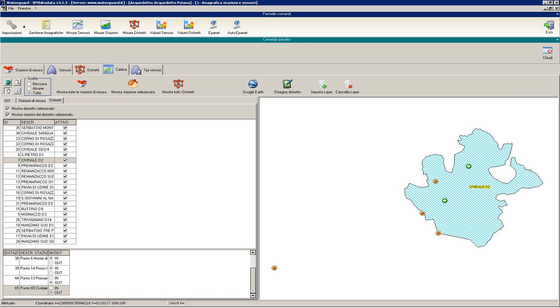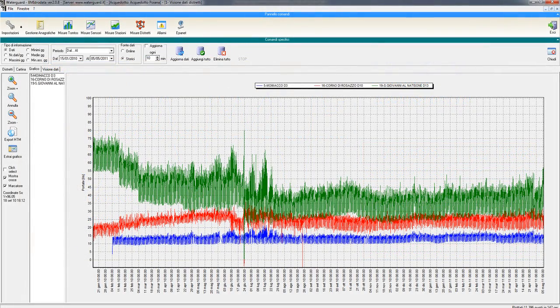The flow rate and network pressure are measured at each single measurement site. This allows you to analyze the data record of a single measuring station individually, as well as to combine measurements with other sites belonging to the same water district in order to estimate the average water consumption of the district continuously. The analysis of the bar graphs of water consumption for every single DMA permits quantification of water losses in that district. Water losses are detected automatically by WaterGuard, while the operator evaluates the time evolution of water losses and its distinctive features — for example, variations between weekdays and non-working days or in different seasons — and finds their causes.